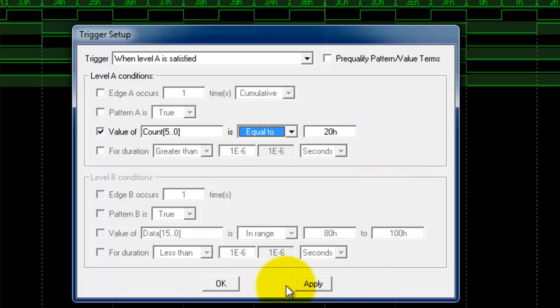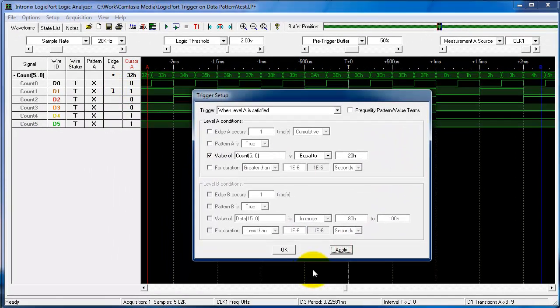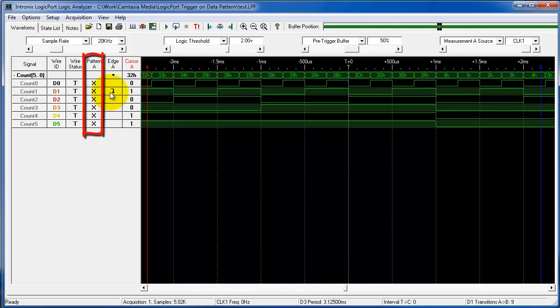I'm going to click apply to do that and I want to let you know that when you come out here you should make sure that in pattern A all the waveforms are don't cares when you do that.